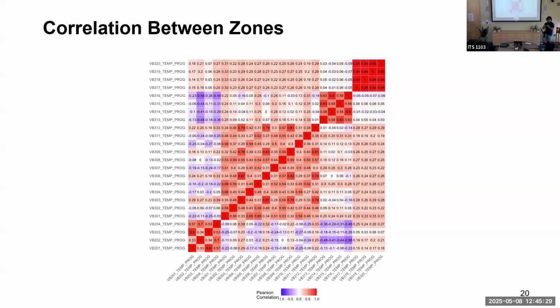Either their temperature goes up and comes down at the same time, or they share a boundary, and then there's some temperature leakage between these zones. So temperature prediction has to be designed in a way that it considers these interactions beyond the single zone, and this is the reason why we are thinking that a data-driven prediction module is much better suited than using something like a physics-based module for these multi-zone large-scale facilities.